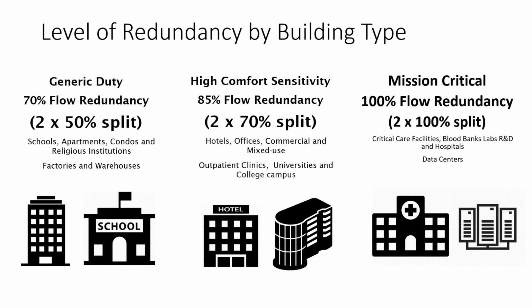I have mission critical applications, and a lot of times engineers don't understand that some mission critical is more mission critical than others. From the design standpoint, your generic duty, which would be your schools, apartments, condos, and religious institutions, a 2 by 50 split is more than adequate with the 70% flow redundancy. In a high comfort, like maybe a very high-end hotel or offices or commercial and mixed uses, like your universities and college campuses, we need to bump that up to a 70% split. So we're still going to be saving a lot of energy, but we're raising our flow rates up, so that way we're able to accommodate the quick changes in temperatures that are necessary in these spaces.